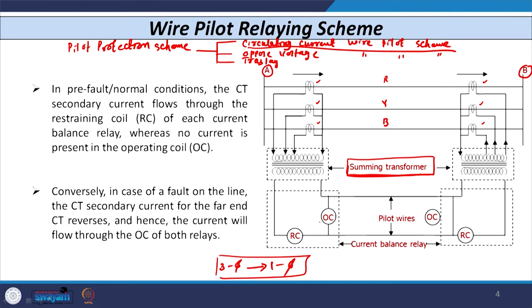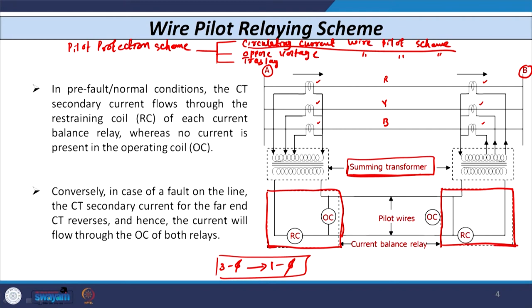After the summing transformer, you have the relay located at each substation — one relay at substation A and one relay at substation B. This relay is a current-based differential relay with two coils: one is the operating coil and the other is the restraining coil (RC). Physical pilot wires connect both substations A and B.